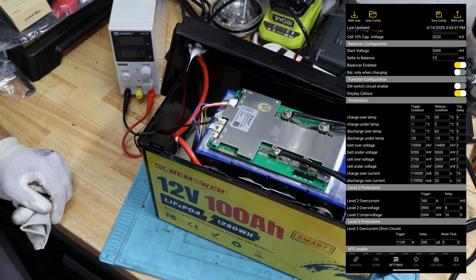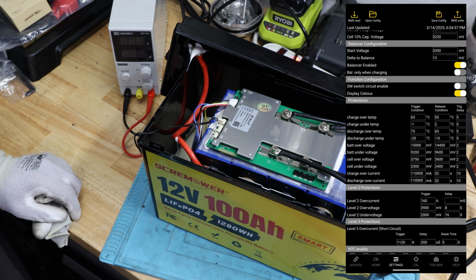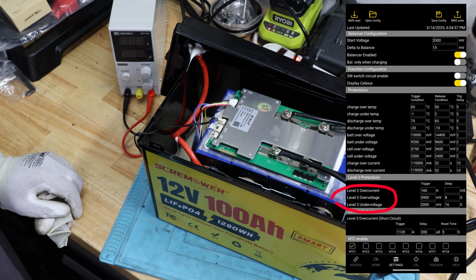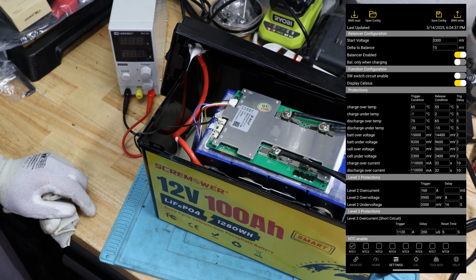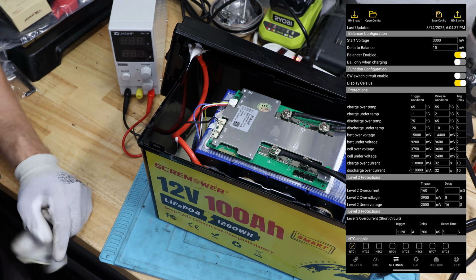And cell under voltage, over voltage, level 2 under voltage, level 2 over current is 160 amps, it's set to 160 amps. I'm wondering if we change that, if we could pull more. Battery is empty, so you can play around with that setting yourself if you want to.